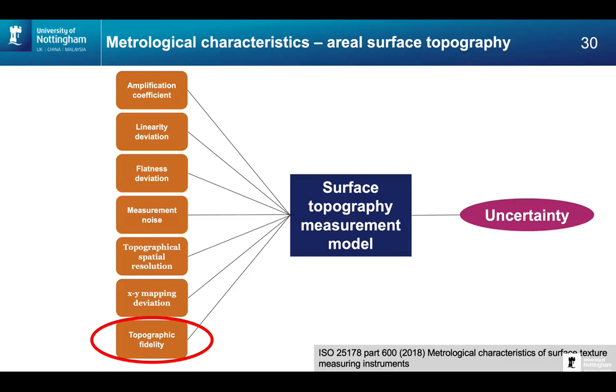Those top six are in ISO 25178 part 600, and that defines them, and then part 700 will tell us how to actually determine them using material measures. But topographic fidelity, and in fact topographic spatial resolution, will not be normative in part 700. We still don't have enough information, or the database, to allow us to work out exactly how to do that and to standardize it.